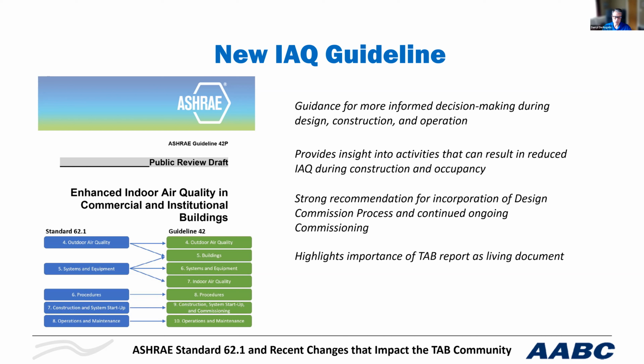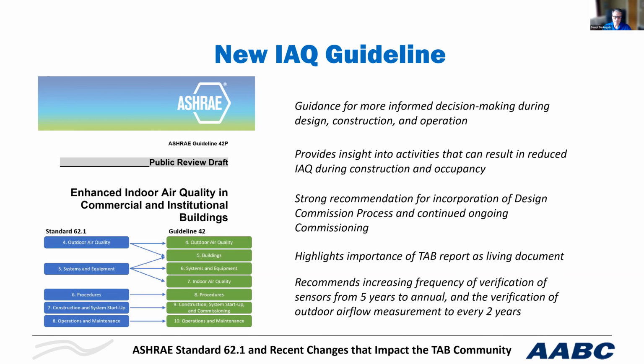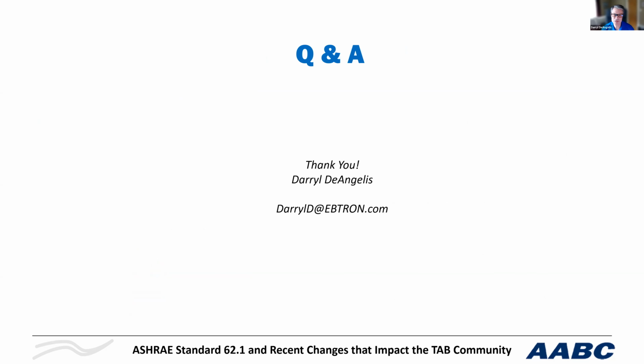We have the requirements to go back and verify, and that's my final point here: it actually enhances the verification. It goes from five-year verification on the outside air sensors to annual verification on these sensors. And it goes to verification of the outside air flow sensors from every five years to two years, because the nature is that things go wrong. So this concludes my presentation, and I'm happy to take any questions you have.